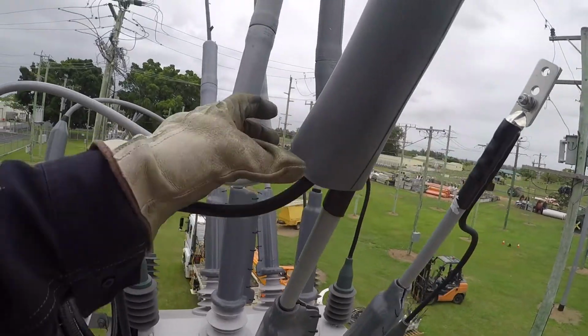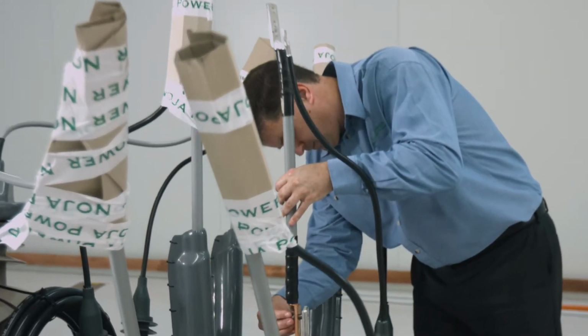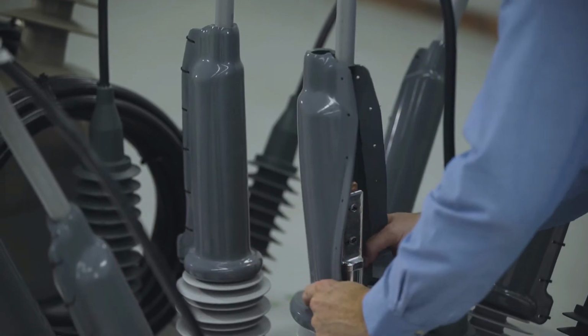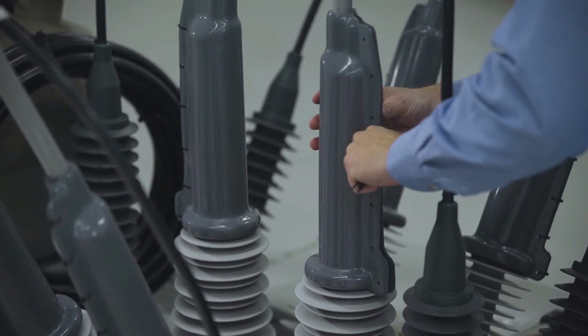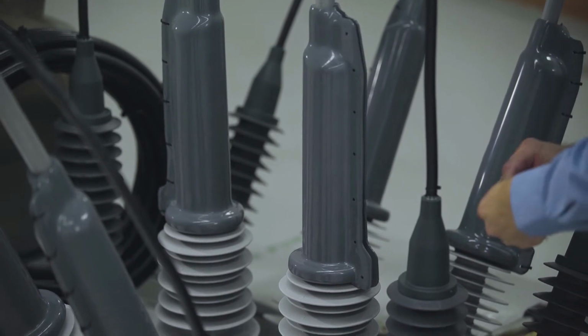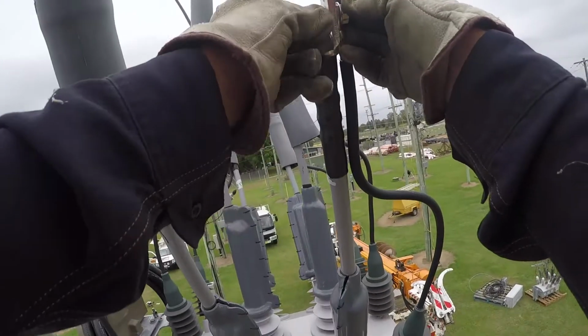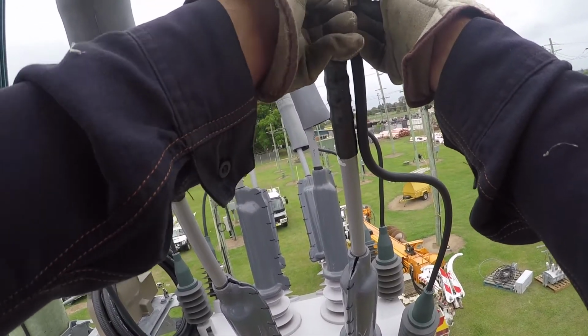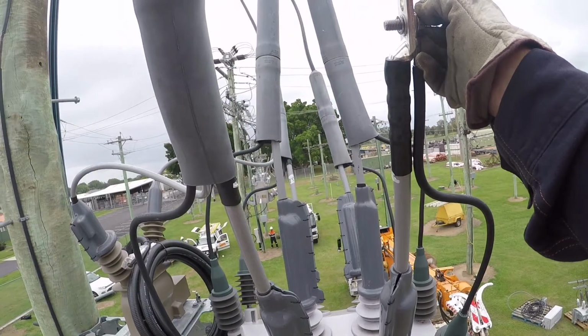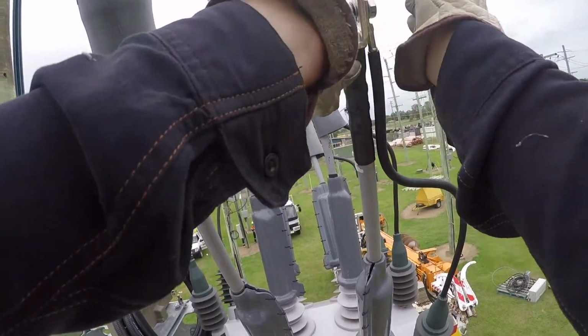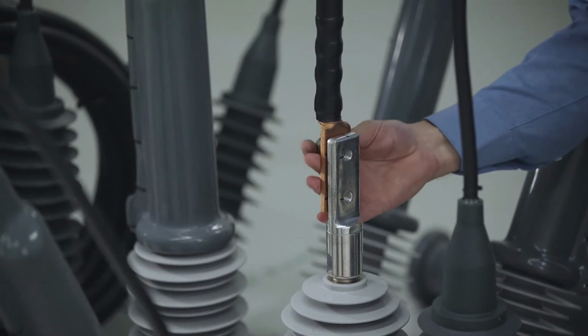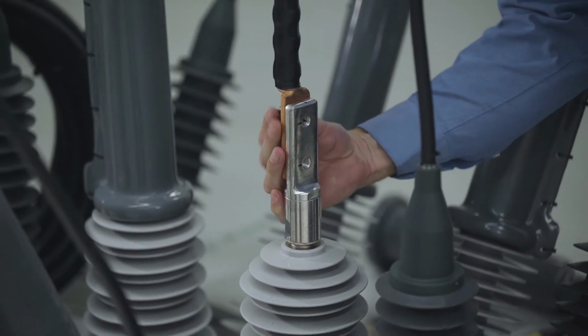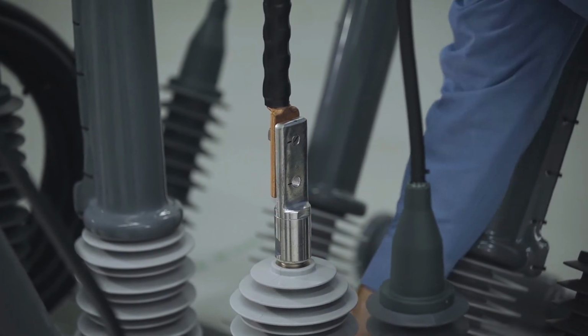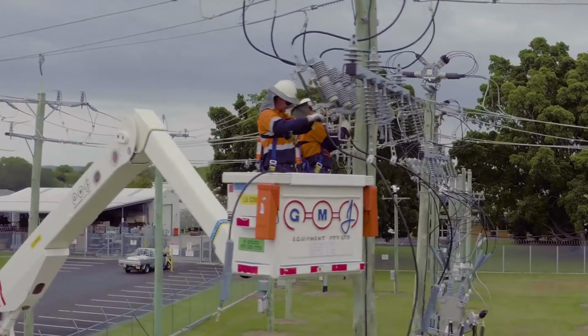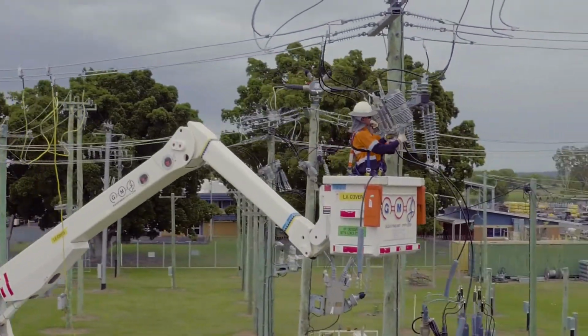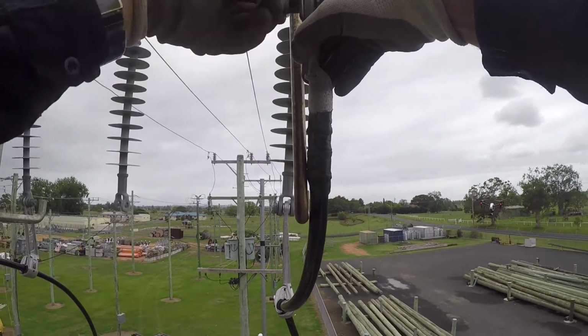NOJA Power recommends that all high voltage connections are done using insulated HV cables and bird guards. This will protect the tank from short circuits caused by animals and will make it easier to keep acceptable clearances in the installation. Connection of the cables to the recloser terminals depends on the type of termination supplied with the recloser. The OSM recloser can be fitted with tunnel connectors or NEMA 2-hole palms. The palm connectors can be supplied with threaded or non-threaded holes. They are intended to be used with appropriate crimp lug connections. The prepared HV cable tails are cut to size at site and can be simply terminated onto the open disconnectors.